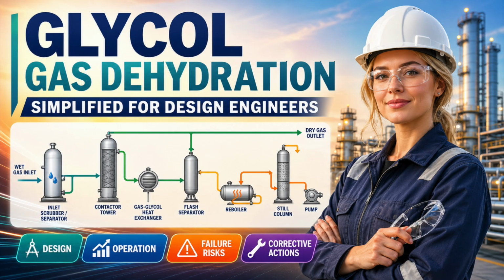A reboiler can produce enough heat and still be badly designed. Excessive heat flux creates local overheating. Poor flame pattern creates hot spots. Deposits on the fire tube reduce heat transfer and drive wall temperature higher. Low glycol level exposes the fire tube. Weak combustion control wastes fuel and increases risk. A removable fire tube is not a convenience, it is part of maintainability.